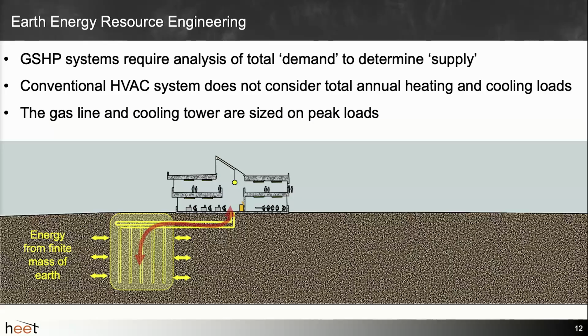So what's the difference between Earth Energy Resource Engineering or geothermal engineering and conventional HVAC systems? Well, the main difference is that for ground source heat pump systems, you should be considering the total demand, right? The total demand of a building, not just a peak of the coldest day of the year or the warmest day of the year, but your total heating and cooling on an annual basis to determine your total supply, because you're designing your source, right?